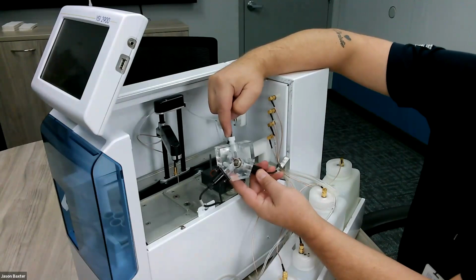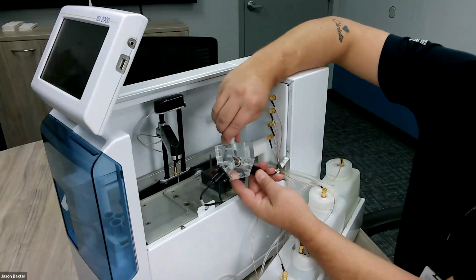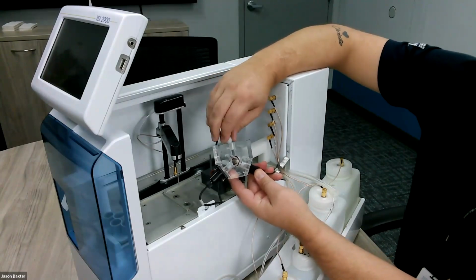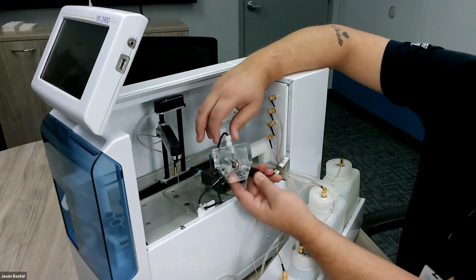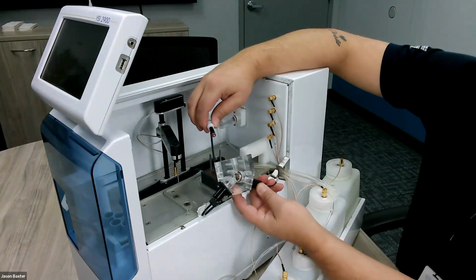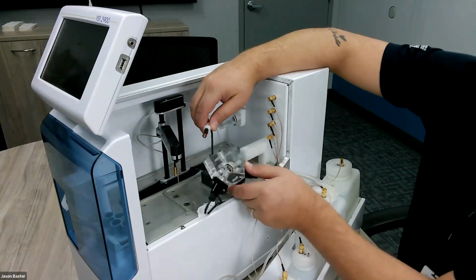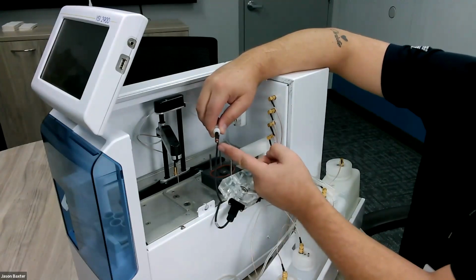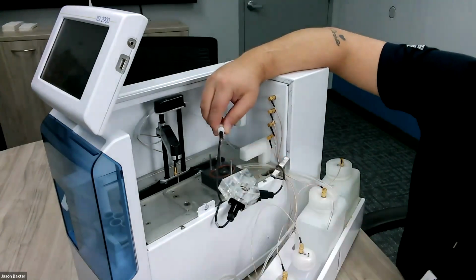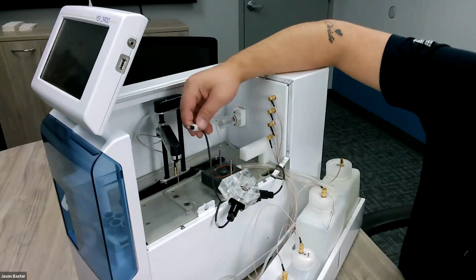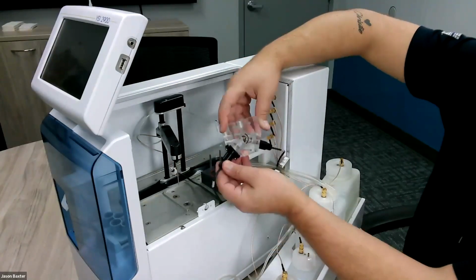Unscrew your temperature sensor, which is your white lead at the top. The thumb screw will just simply unscrew, and then you can simply lift the temperature sensor out. You'll notice there's an O-ring on the end of the temperature sensor. That O-ring is removed and discarded. Set your temperature sensor down.